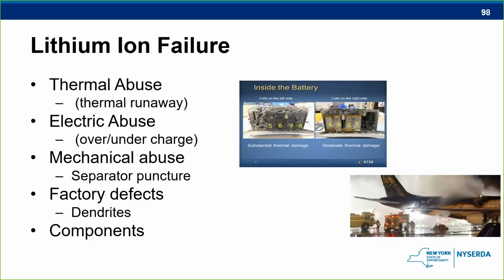But if it continues to go, you'll get a cell that will go into thermal runaway. The moment it goes into thermal runaway, you can't stop it. It just continues to go, and that heat will actually transfer to the adjacent cells. And it was a good visual that Jennifer presented, but that thermal runaway is a concern for us. Once we have that heat transferred to the next cells adjacent to it, then sure enough, those things go into a thermal runaway event, and then it continues to propagate throughout the module itself. And then we could have it going from module to module, and that becomes a big problem for the fire service.